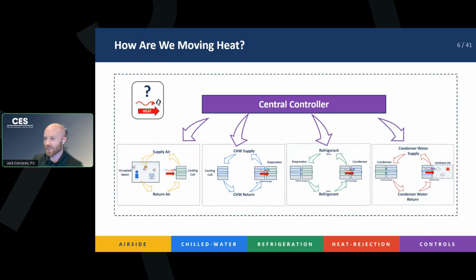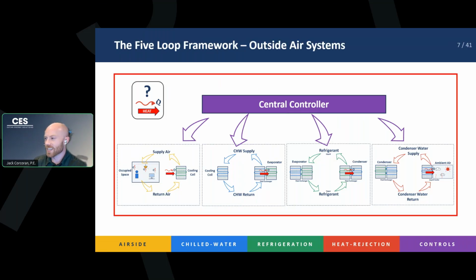And back to our theme of all of our presentations, right? If we're adding in a heat load, how are we going to move that heat back outside? Some way, some combination of these 5 system loops, as introduced by Trane in their HVAC clinic. We're adopting it here because it's a really good way to explain these sorts of systems. The 5 loops are along the bottom. Which one are we actually going to be using for our outside air? Which combination, 1, 2, 3, or more? We can actually use any combination, right?